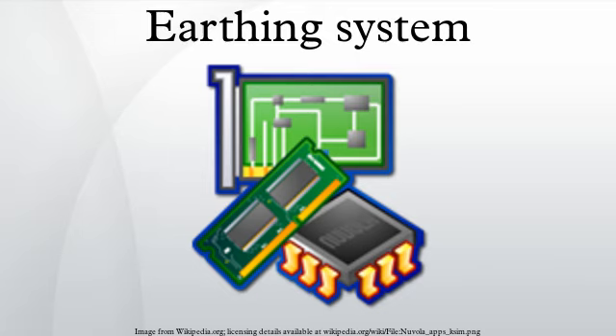In electricity supply systems, an earthing system or grounding system is circuitry which connects parts of the electric circuit with the ground, thus defining the electric potential of the conductors relative to the Earth's conductive surface. The choice of earthing system can affect the safety and electromagnetic compatibility of the power supply. In particular, it affects the magnitude and distribution of short-circuit currents through the system, and the effects it creates on equipment and people in the proximity of the circuit.